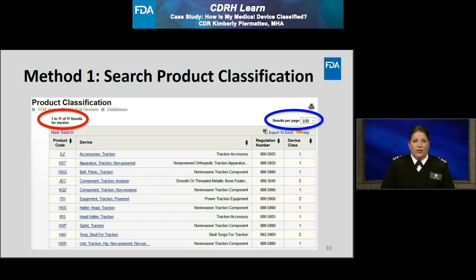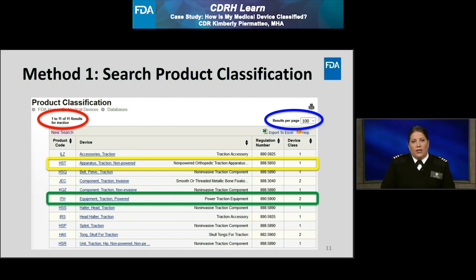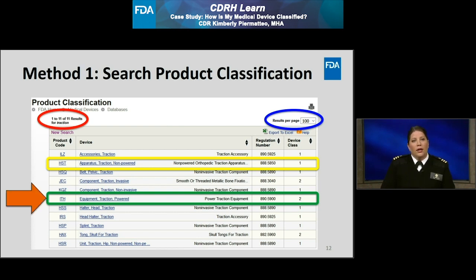I could review each product classification to determine if it applies to my traction device, or I could further define the intended use of the traction device so that I can narrow down the results even faster. For this example, I'm going to clarify the intended use of the traction device to indicate that it is a powered traction device. Now looking at the results, I see there is a product classification for a non-powered traction apparatus highlighted in yellow on the slide. But then, there is a more applicable powered traction equipment highlighted in green below. Therefore, the ITH product code looks to be more applicable to my powered traction device.